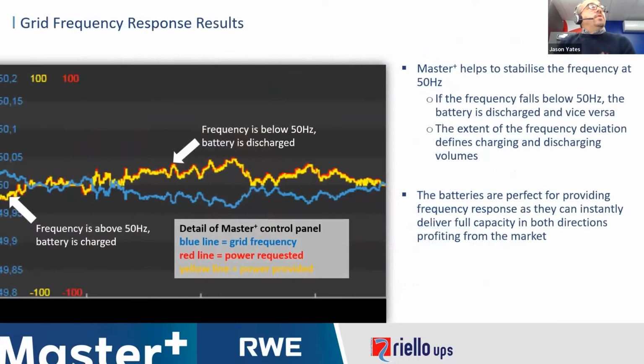So how did it work? Well, this is data taken from one of the live systems. As you can see, the blue line represents the grid frequency, the red line represents the power demanded from the system, and the yellow line represents the power being provided by the system. As the frequency increases above 50 hertz, we take power from the grid and push that power into the battery system. Then, when the grid frequency falls below 50 hertz, we take the power back from the battery and push it back into the grid again. Therefore, we help to stabilize the grid by either taking power from the grid when the frequency is high or pushing power back into the grid when the frequency is low. The UPS system then operates for frequency response, to balance the grid frequency.